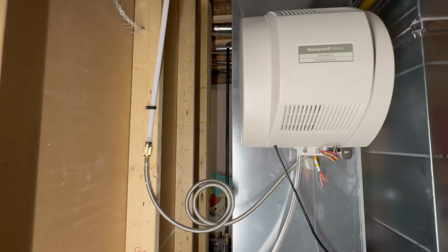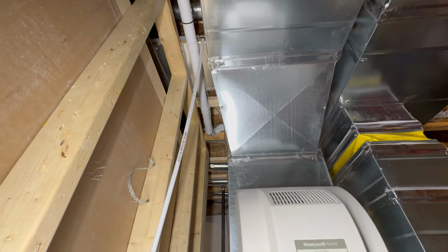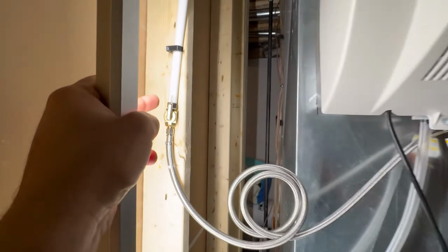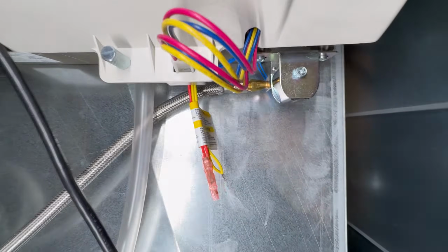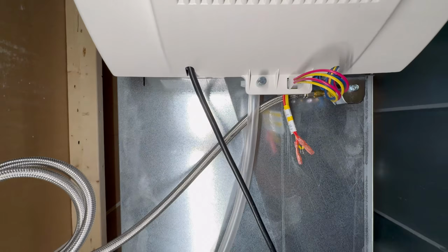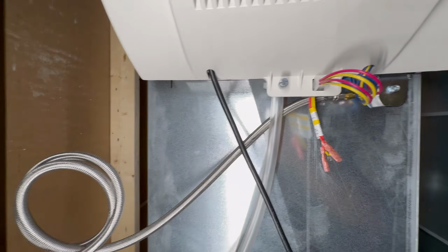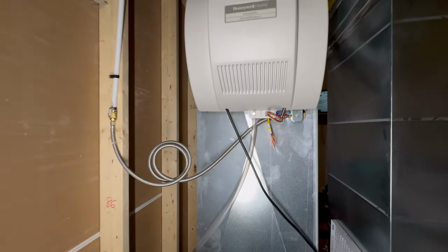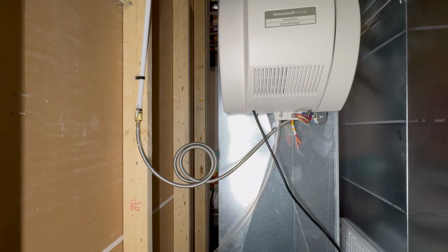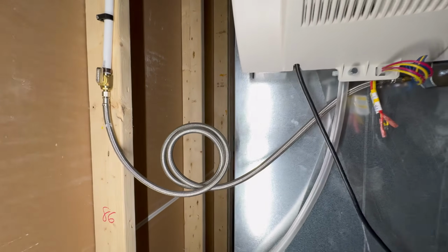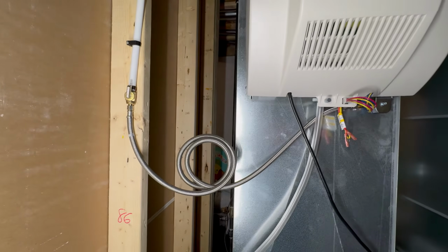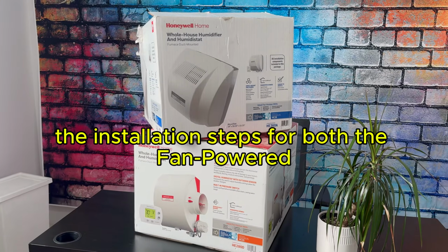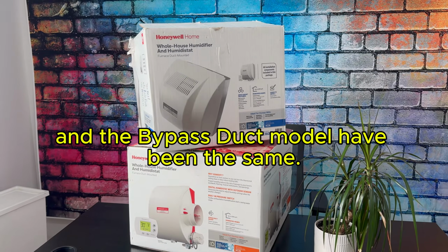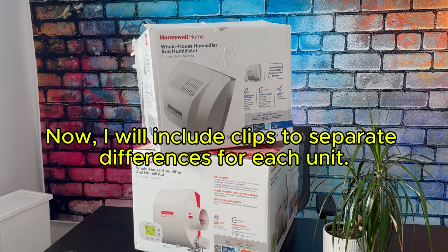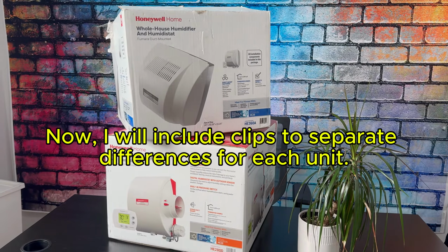And so what I've done is I've connected a water line using a PEX T, and I've added a valve here, and I have a 1/4-inch braided line that runs straight to the solenoid. This way, we avoid any sort of leaks with the plastic piping, as well as a saddle valve, which is known to have leaks. They're very prone to leaks, and they're very frowned upon in the plumbing industry. So I highly recommend a braided water line for this connection. Up to this point, the installation steps for both the fan-powered and the bypass duct model have been the same. Now, I will include clips to separate differences for each unit.